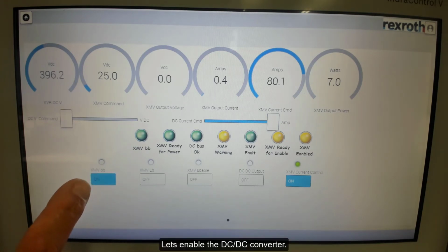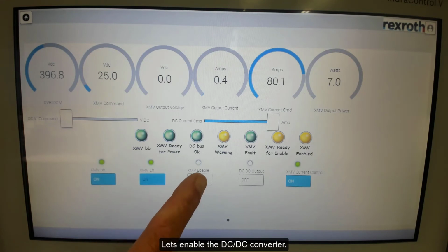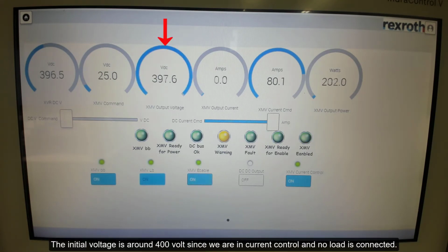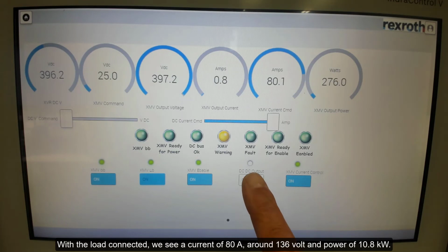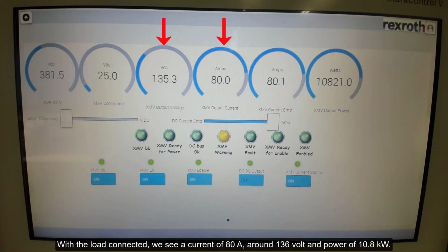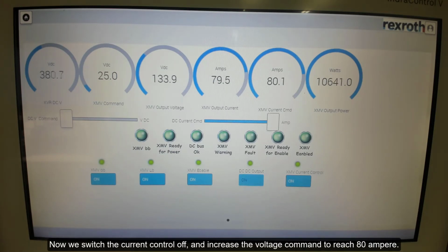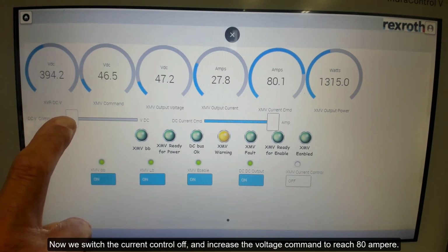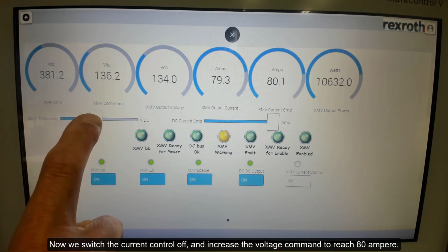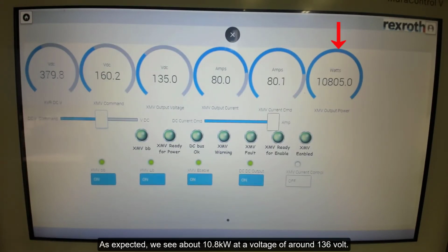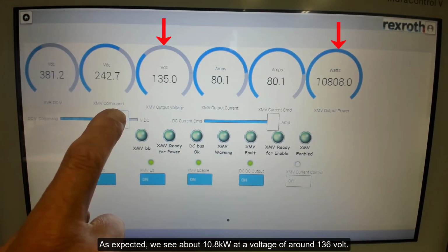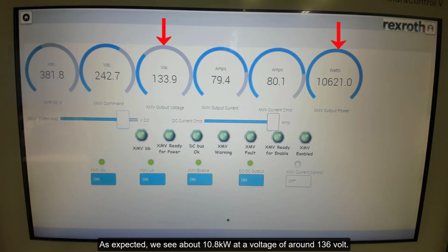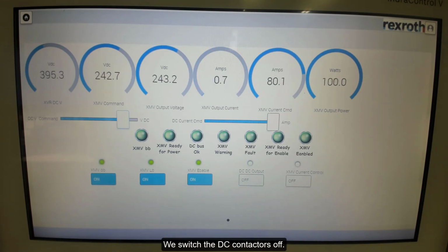Let's enable the DC-DC converter. The initial voltage is around 400 volt, since we are in current control and no load is connected. With the load connected, we see a current of 80 ampere, around 136 volt and power of 10.8 kilowatts. Now we switch the current control off and increase the voltage command to reach 80 ampere. As expected, we see about 10.8 kilowatts at a voltage of around 136 volt. We switch the DC contactors off.